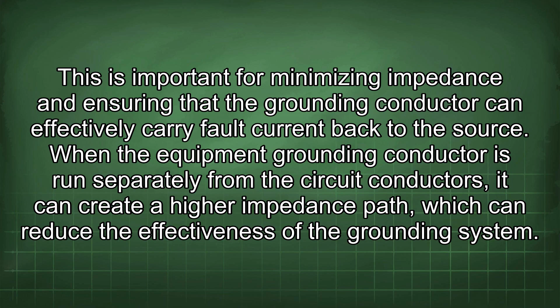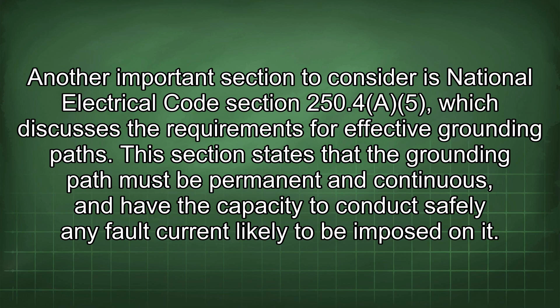Another important section to consider is National Electrical Code Section 250.4(A)(5), which discusses the requirements for effective grounding paths. This section states that the grounding path must be permanent and continuous and have the capacity to conduct safely any fault current likely to be imposed on it. This reinforces the importance of using properly sized grounding conductors and making sure that all connections are tight and secure.